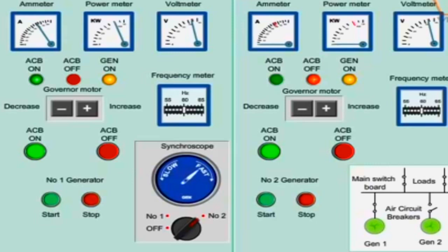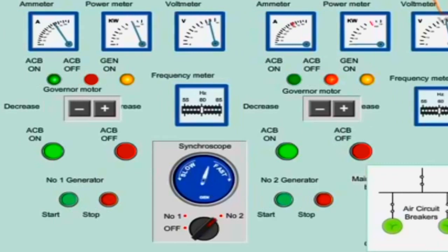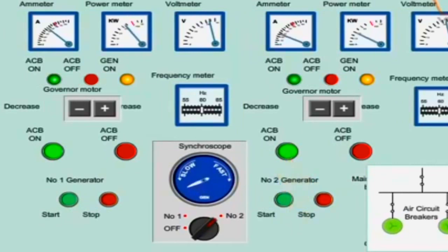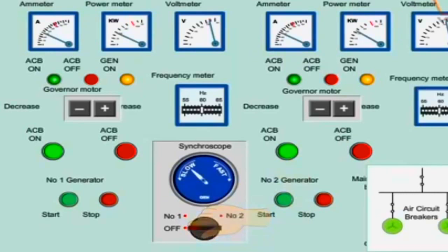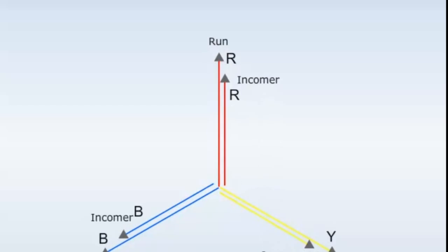The actual synchronism between the two generators is indicated by the twelve o'clock position on the synchroscope. Close the air circuit breaker when the needle reaches the 11 o'clock position, taking into account the breaker closing time.